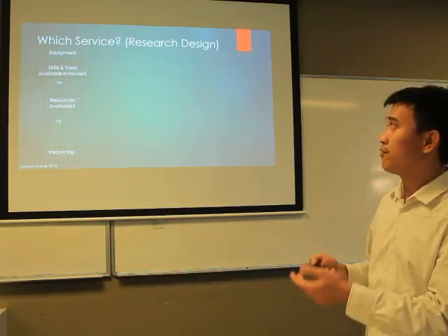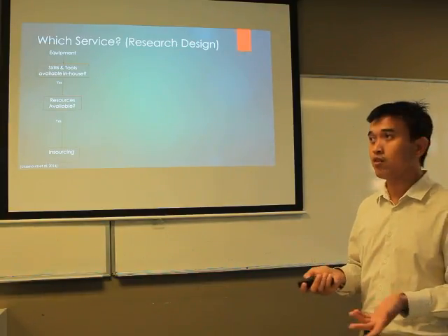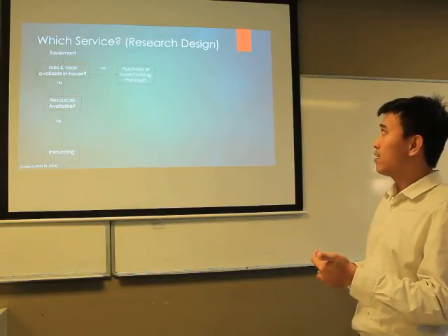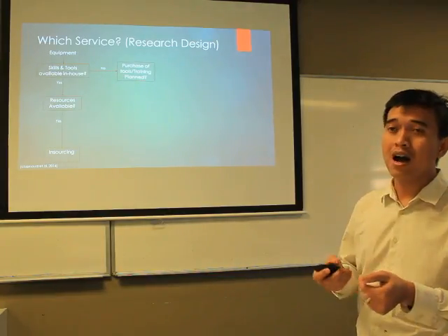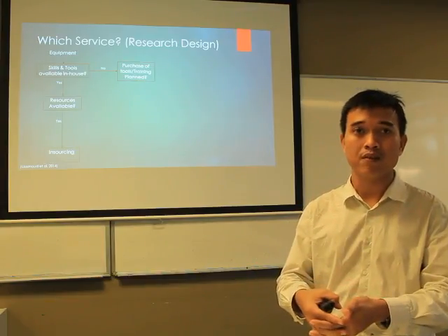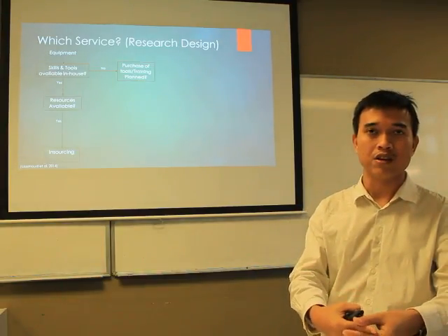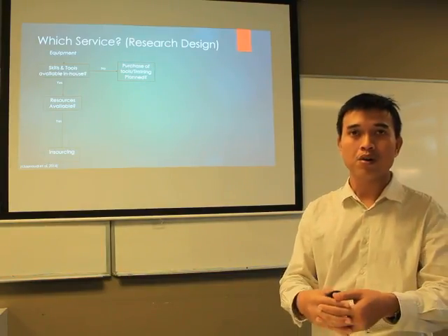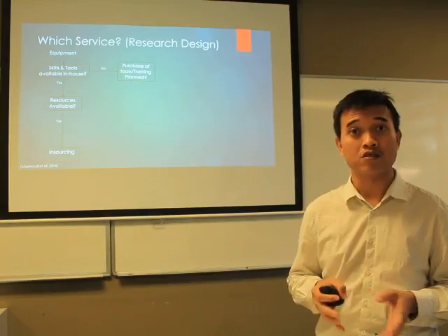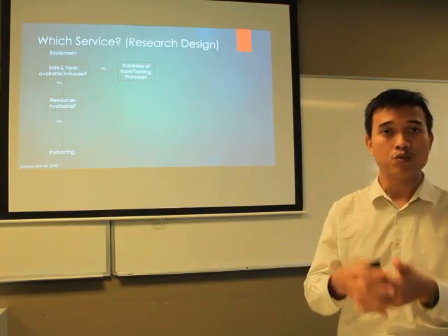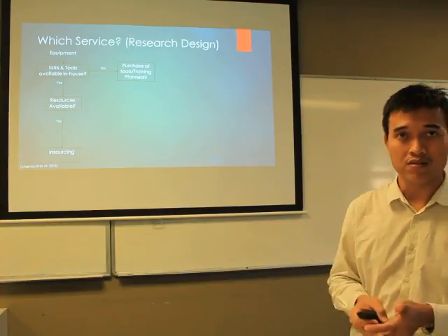If we don't have the skills or tools available, we have to think of another thing, which is whether they are available to be purchased, which means can we purchase the spare parts, and for manpower, can we conduct training for our technicians to do the maintenance by ourselves?